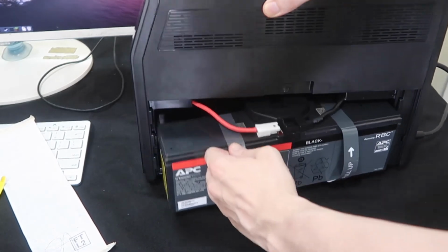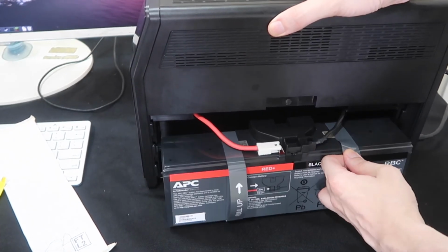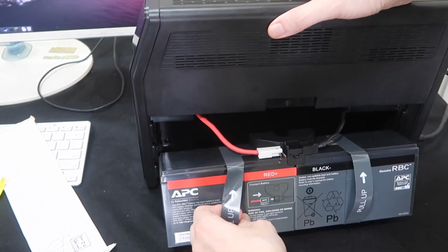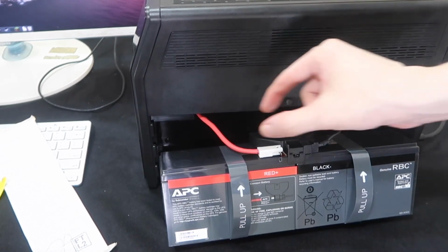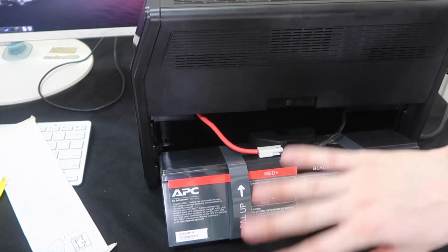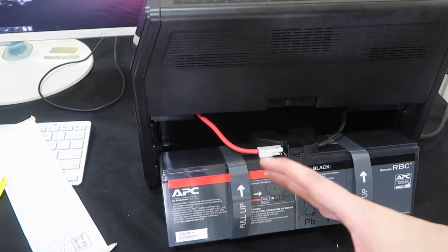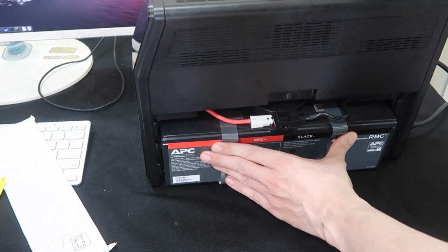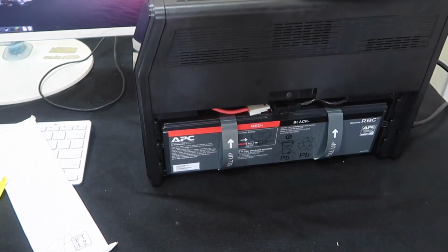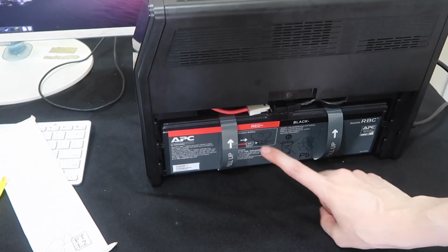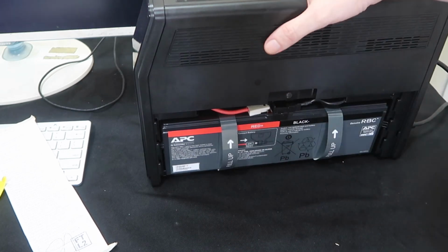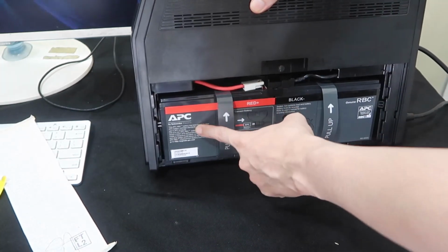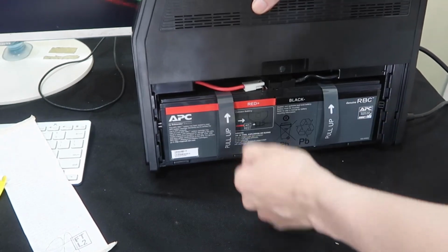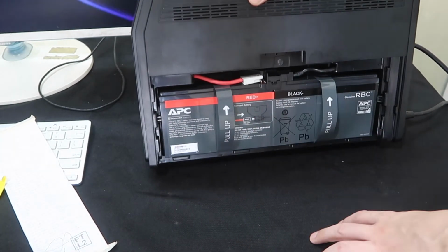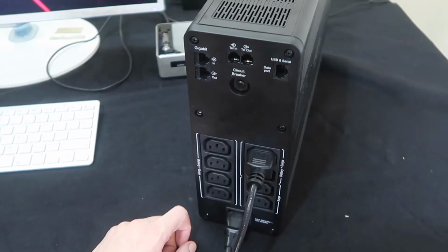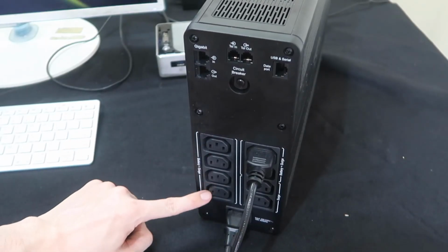Unlike some UPS where you need to use a screwdriver to open the unit, this one is extremely simple. You see, you can just pull it out like that, disconnect, and then put in the new battery. Of course, make sure you shut down the UPS before you do that. And that is something to be aware with any UPS, that eventually you will have to replace the battery because lead acid batteries don't last forever. But I can say that APC, the quality of their batteries is so, so, so much better than the cheap generic UPS.